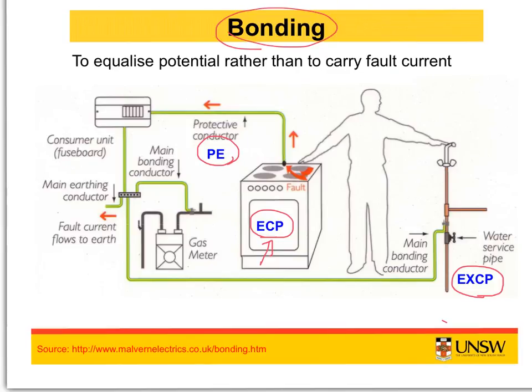So the protective earth conductor is a conductor provided for the purpose of safety against electric shock. Its function is to safely drain the fault current to the ground. This is also referred to as the equipment grounding conductor. Now bonding ensures that all the conducting metals, all metal parts in the house, for example the EXCPs, ECPs, everything, are maintained at the same potential. The purpose of bonding is therefore to equalize the potential between the various metallic parts.